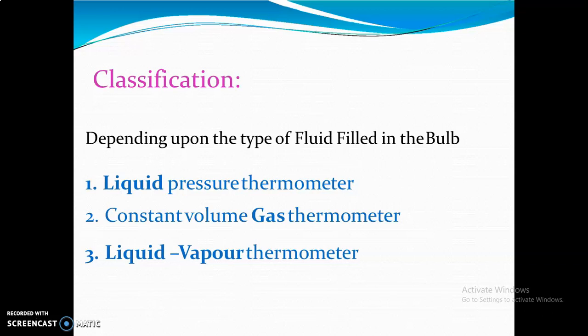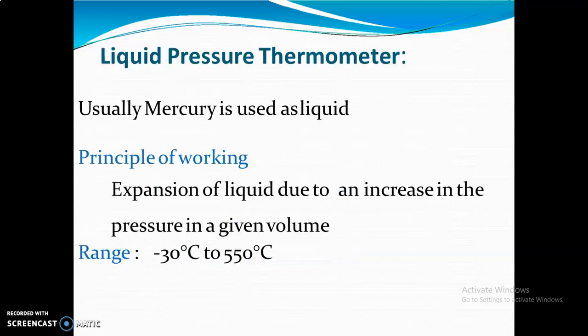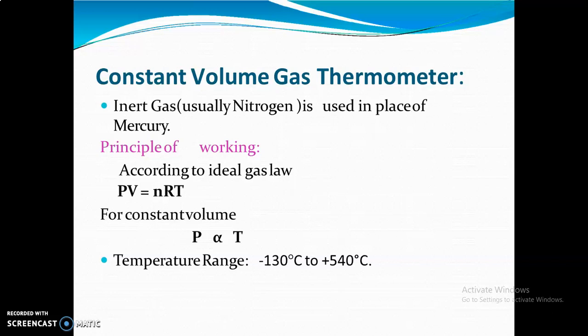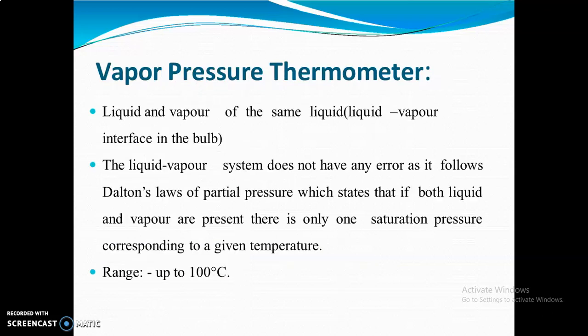These are the different types. For liquid pressure, mercury is used and the range is minus 30 to 550 degrees centigrade. For constant volume gas, the formula is used and P is directly proportional to temperature; the temperature range is minus 130 degrees centigrade to 540 degrees centigrade. For the vapor pressure thermometer, liquid and vapor of the same liquid are used. It does not have any error as it follows Dalton's law for partial pressure. The range is up to 100 degrees centigrade.